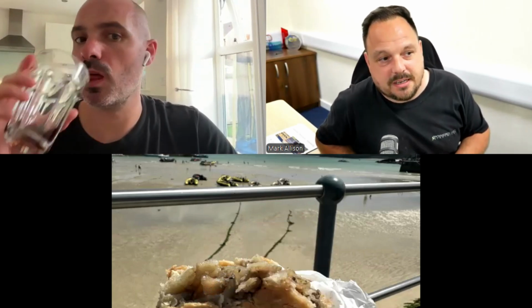I know from speaking with someone who does install heat pumps that there's one manufacturer - I won't say who - that does stipulate in their instructions you have to install a type B RCD. This caught him out on a job because he thought you could use a normal type B RCD, but as it turned out you couldn't. He had to get a specific one from a particular supplier, and it cost like 350 to 400 quid, a cost he wasn't anticipating. Obviously that then falls on the installer or the customer if you realise before you quoted the job.